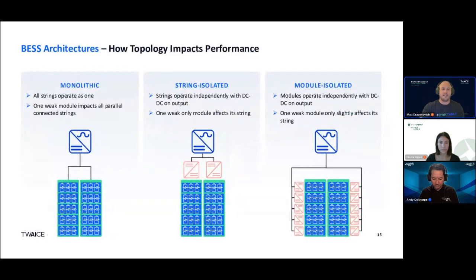A little note on architecture: FE3 was actually one of the first systems we onboarded with a more modular architecture. Many systems we work with have a classic monolithic architecture, essentially many strings or racks connected in parallel to one power conversion unit. If any of those racks or strings have an issue, at the cell or module level, whether imbalances or a failure, it can take out all strings or racks connected in parallel.